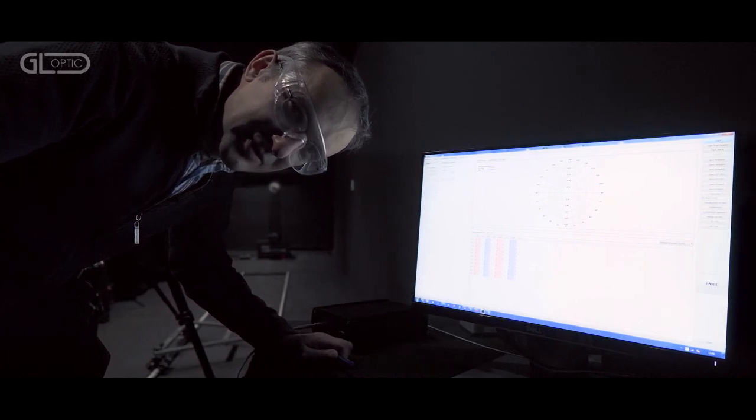Of course, there's one more thing. We have to make sure that the stabilization is done, so we need to pre-warm the lamp, especially as this is a mercury discharge lamp. It will take some time to get it stabilized, and we also should look at the radiant flux for stabilization parameters. So irradiance will be measured, and once it's stabilized, the measurements will start on their own. We are ready to start the measurement, but before that we need to evacuate the room, of course. Safety first.